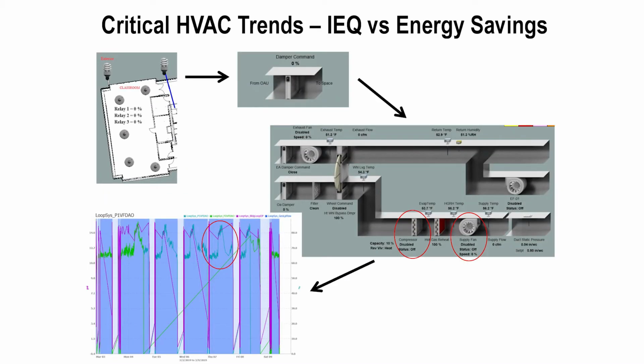When we decided which trends we wanted to look at, we talked about critical sensors. If you have an economizer sequence that relies on enthalpy, you might want to look at that relative humidity sensor and do regular calibrations on it. In this facility, outside air temperature and relative humidity are important sensors to look at.